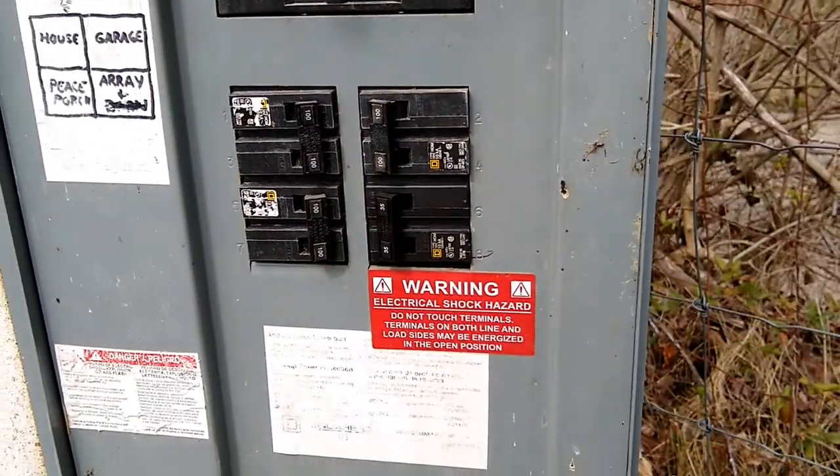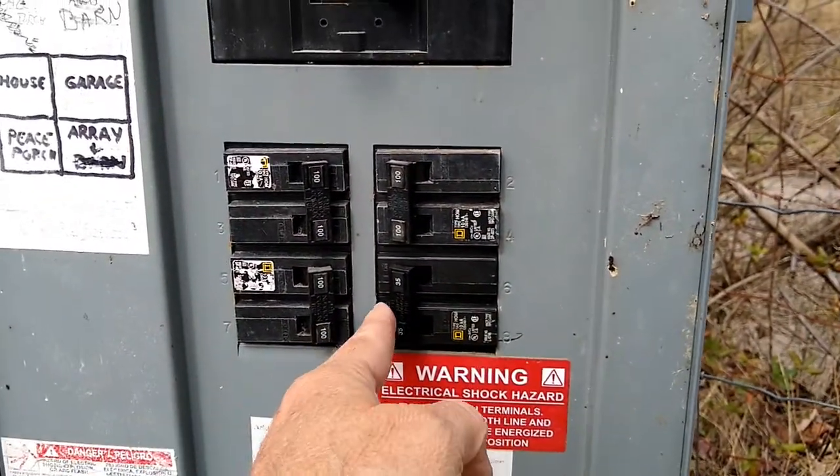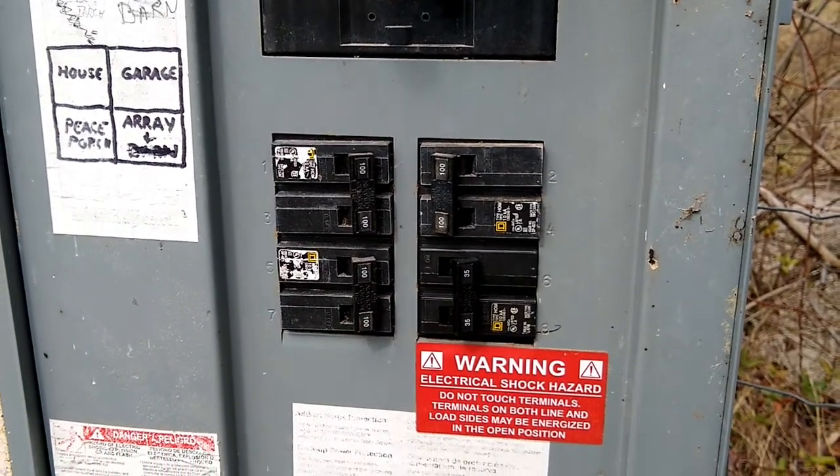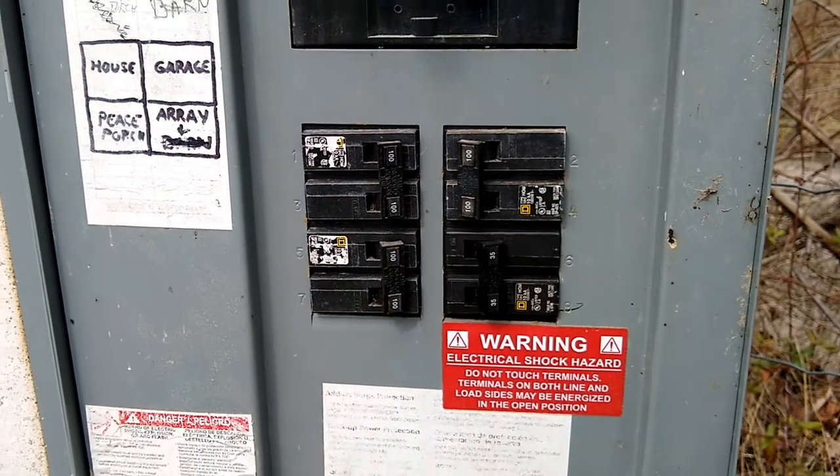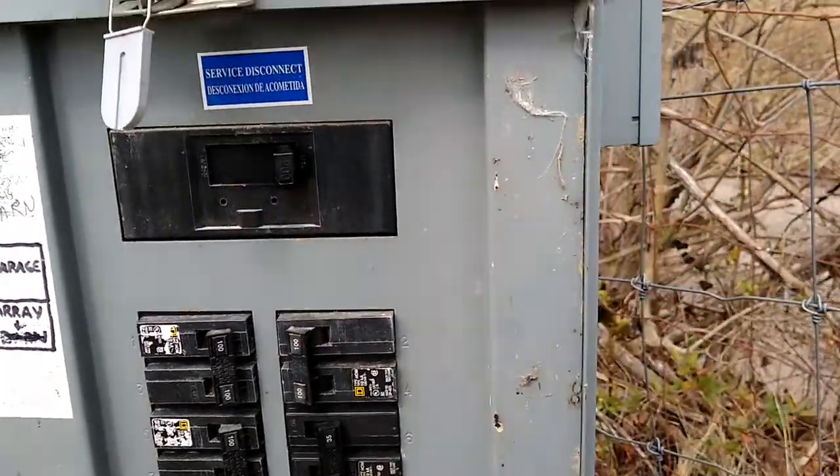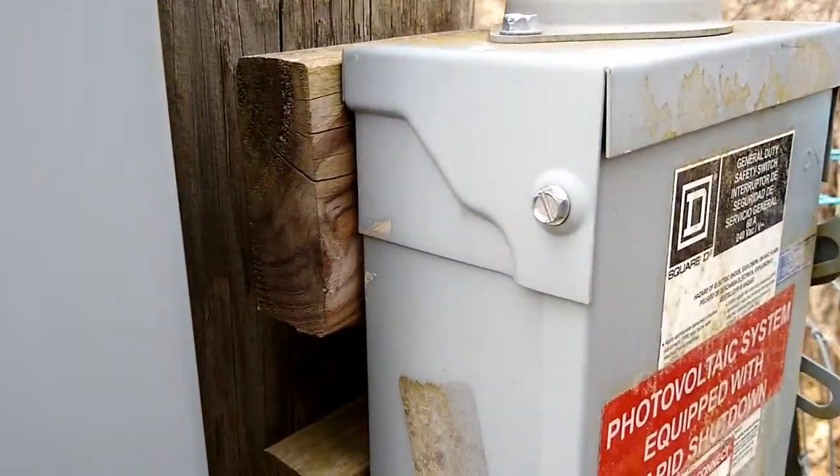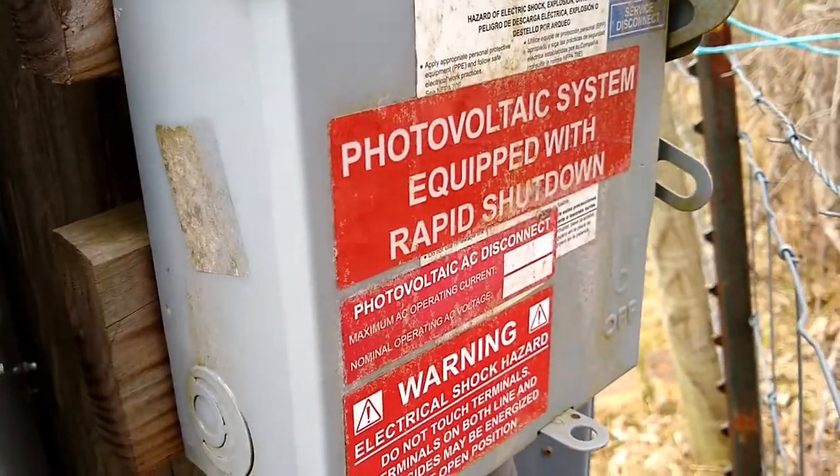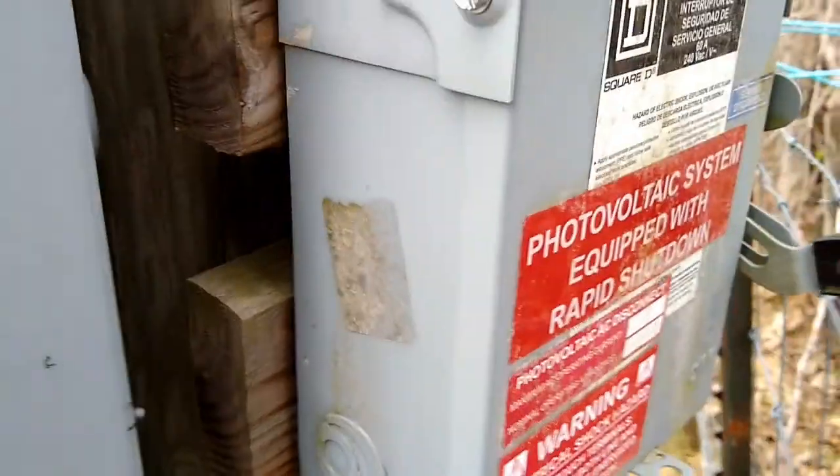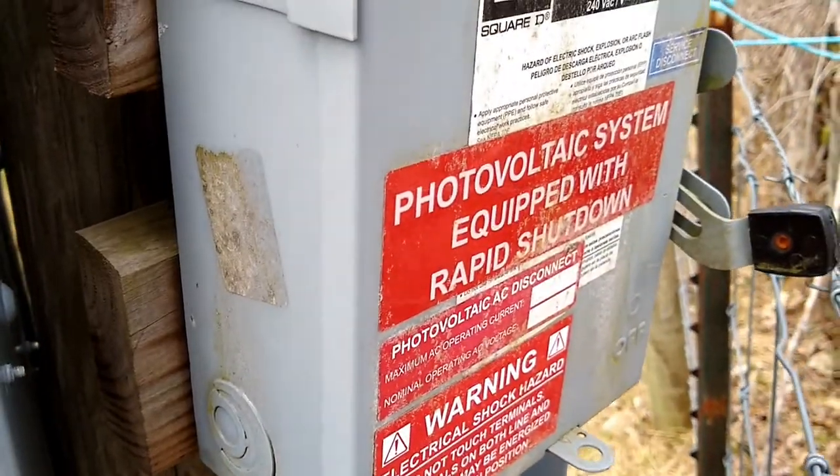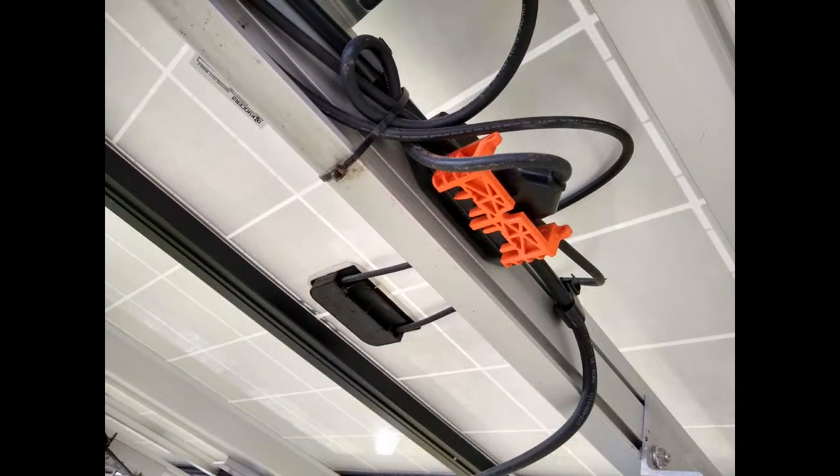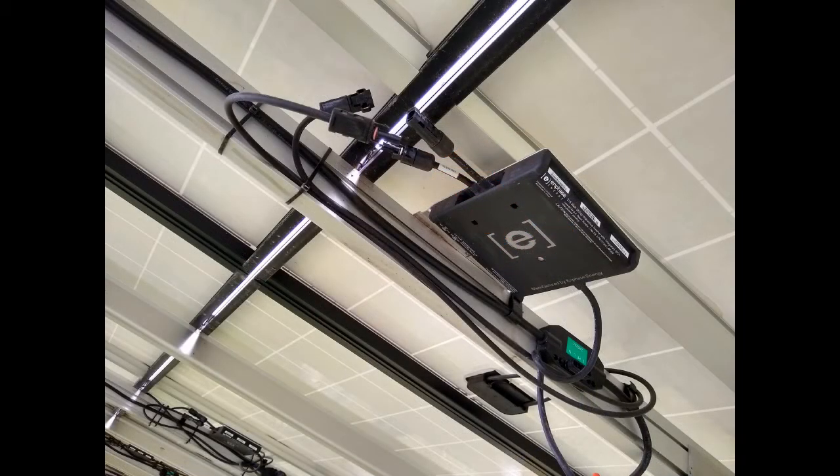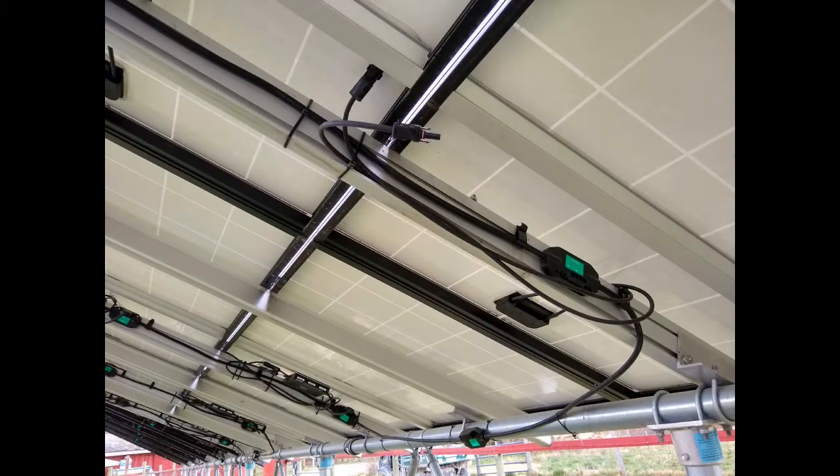Go up and turn the system off at the panel, and then of course I turned off the AC disconnect just as a redundant thing - turning off two switches there, don't want there to be any connection to the grid. Once the grid is turned off then the microinverters will shut down themselves and will not be generating any power. First I disconnected the bad microinverter using the little tool from the proprietary cable, then you disconnect from the panel.